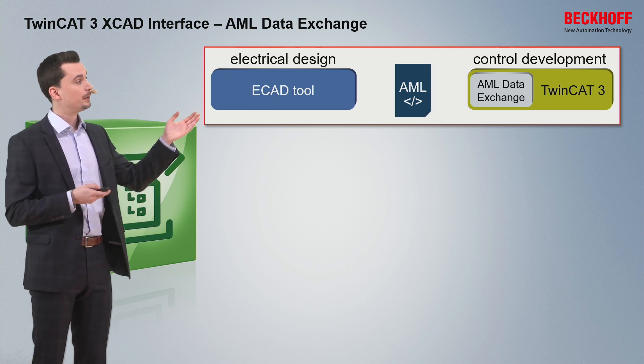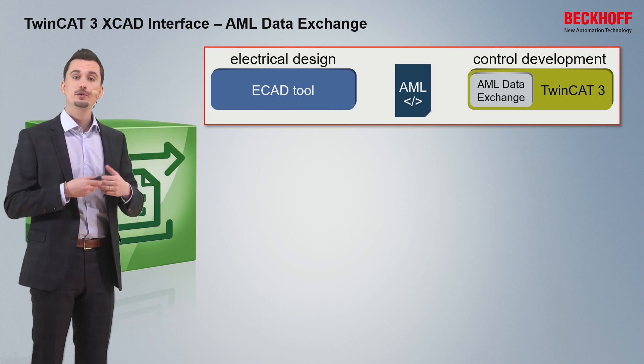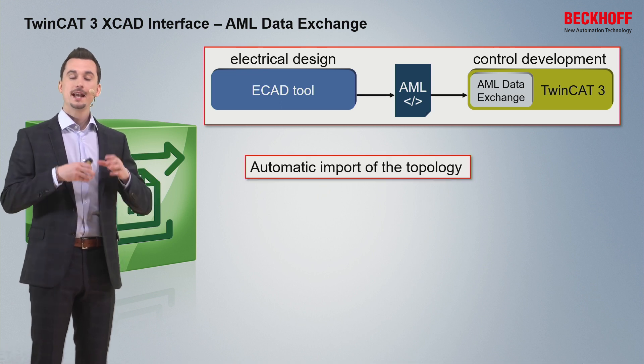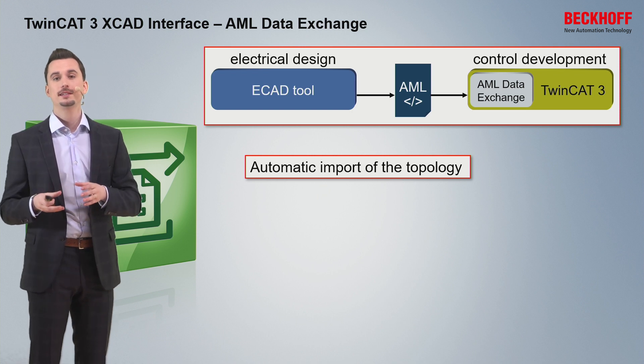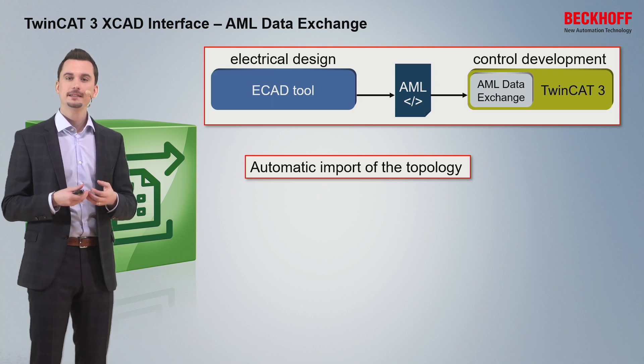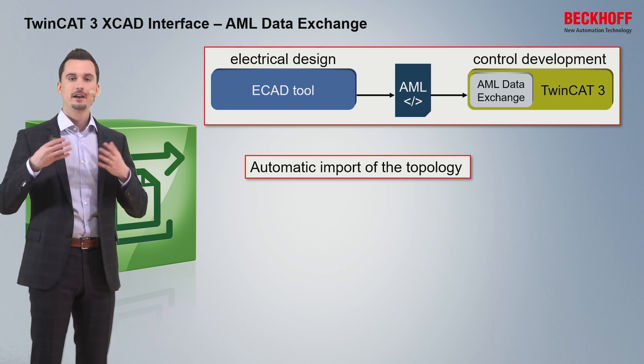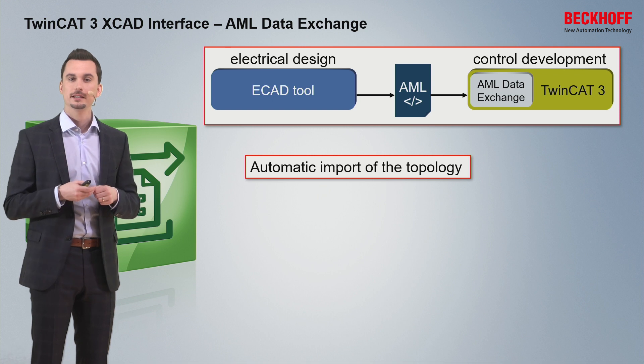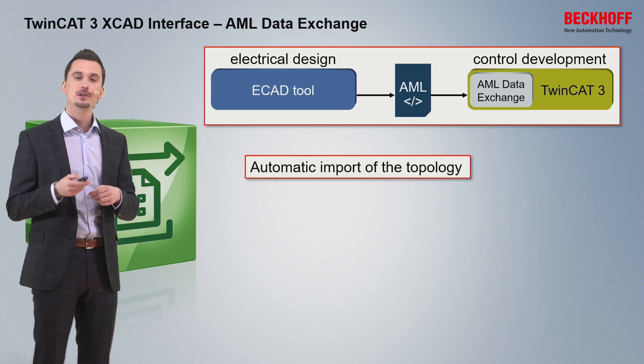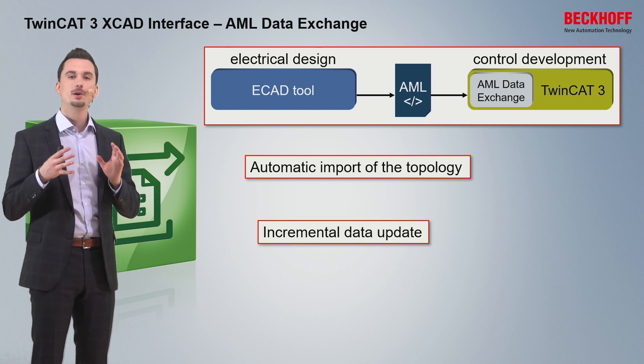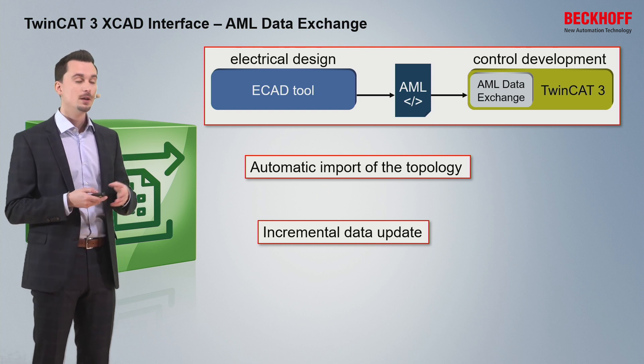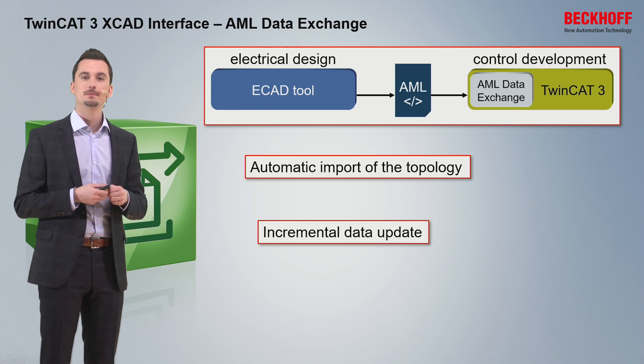If you have your IO topology ready on the ECAD tool side, you can simply export it and import it on the TwinCAT 3 side, and the whole IO topology is then automatically created without having to add anything manually. With the help of unique AML IDs, it is possible to uniquely specify each component added to the AML format, which enables an incremental data update.